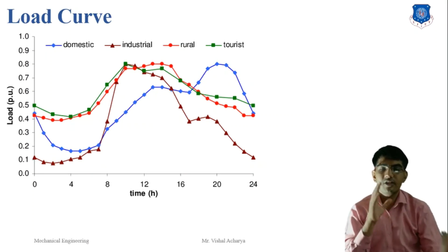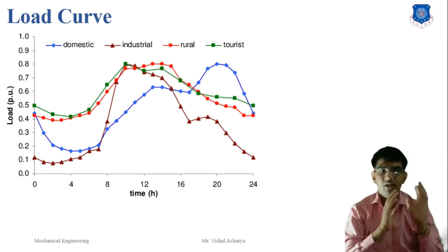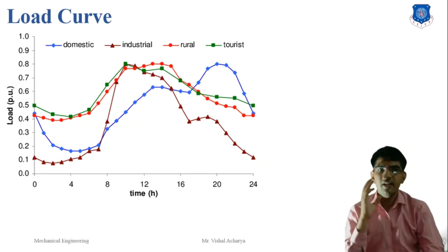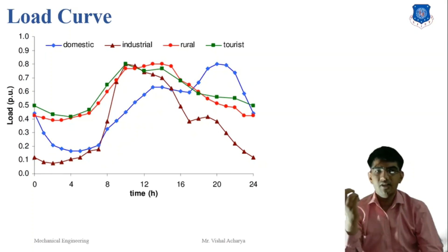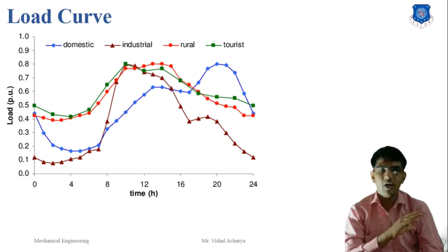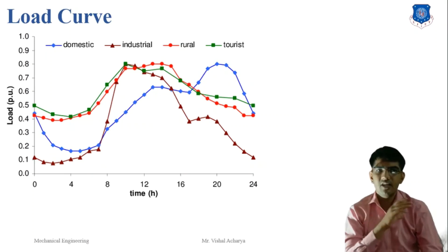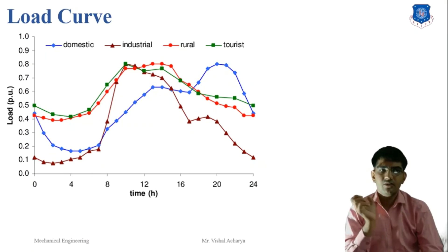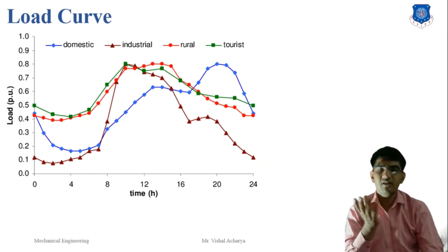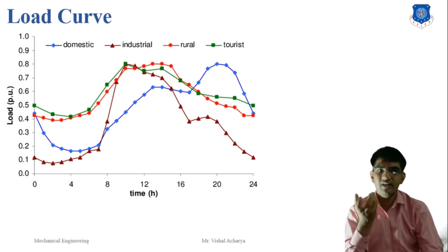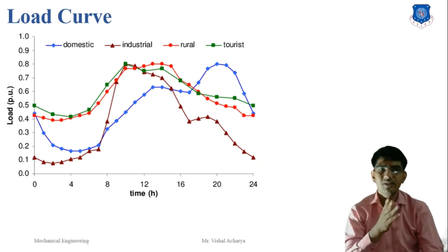Some information obtained from the load curve: First, the load curve determines the load variation during different hours of the day. Second, it indicates the peak load, which determines the maximum demand on the power station. Third, the area under the load curve gives the total energy generated in the period under consideration. The area under the curve divided by the total number of hours gives the average load, and the ratio of that area to the total area of the rectangle containing it gives the load factor.